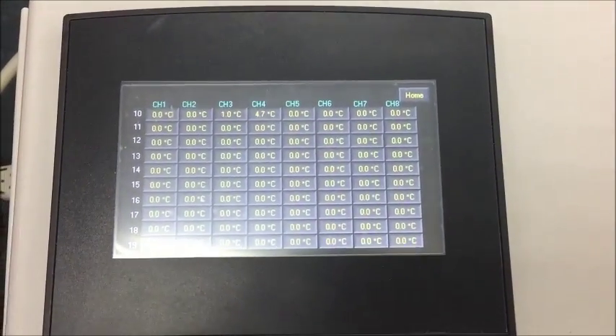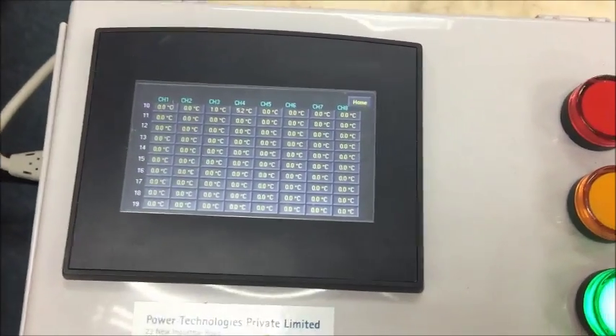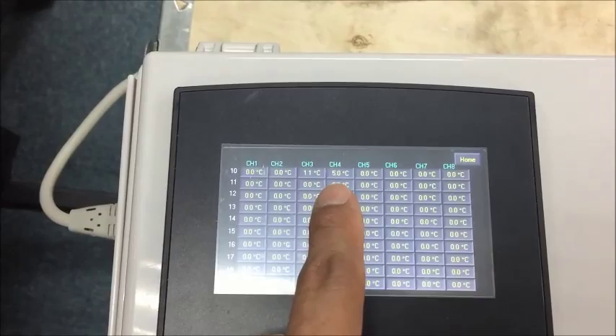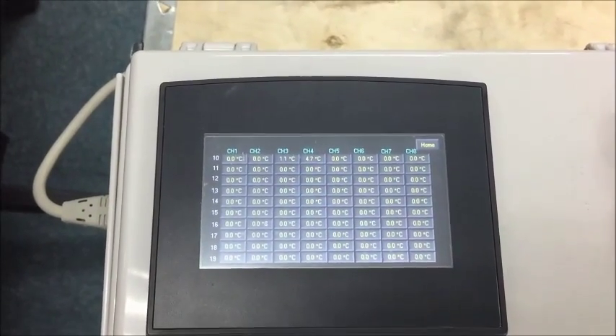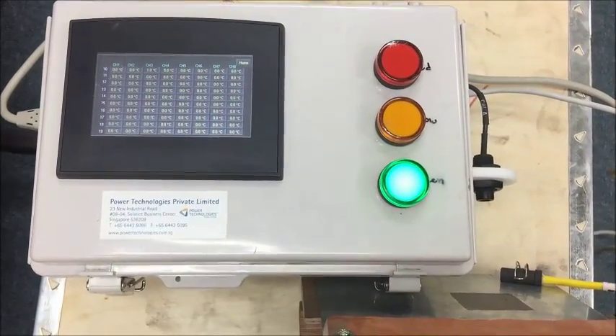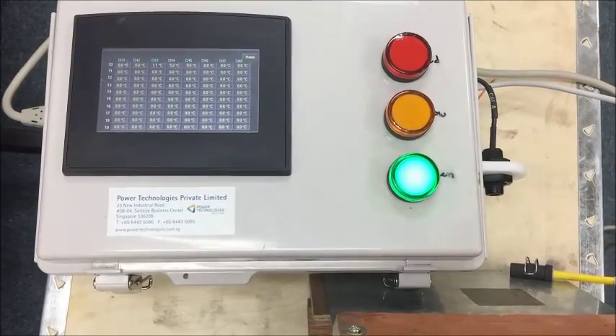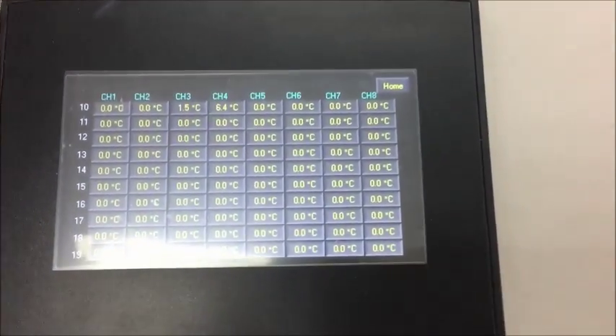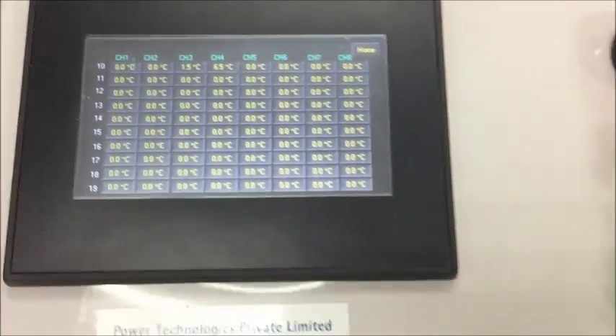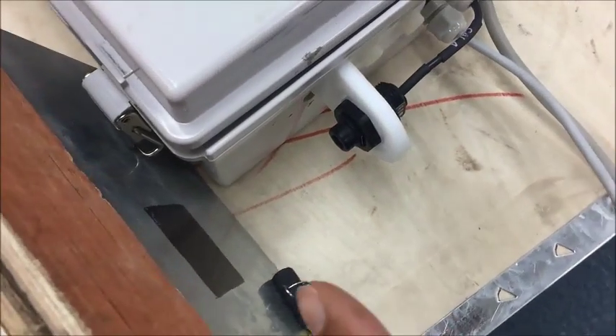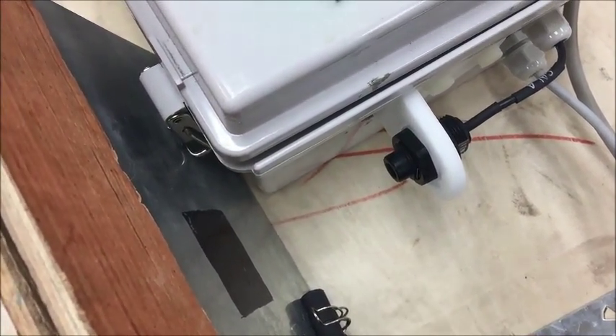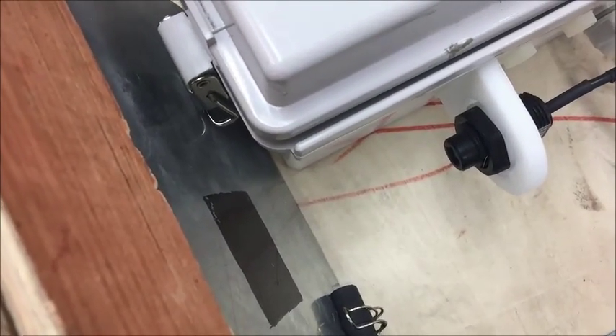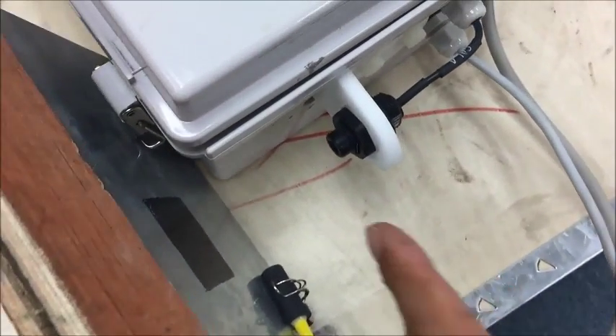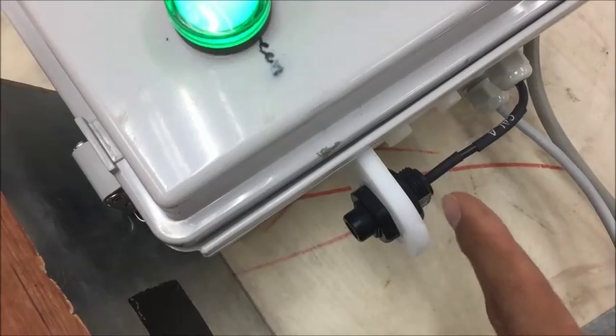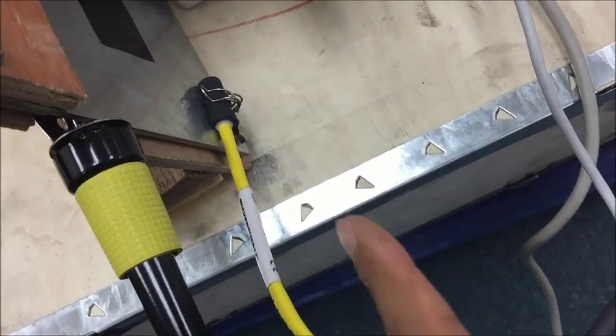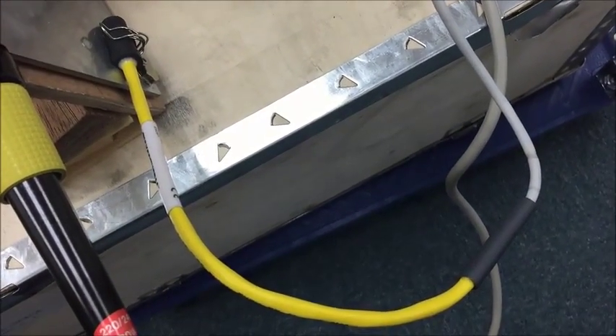We are doing a simulation. As part of this connection the temperature will rise, so the sensors are picking up the delta T difference. It takes a while to pick up. For the cable sensor, the conduction will be slower, as it's a bit different from infrared, because infrared receives whatever the hot surface emits, and it's a very fast response. But the working principle is still the same. In front is infrared, behind is a thermocouple, which measures the delta T difference. Same for the cable sensor, there's one here, and behind there's another one.